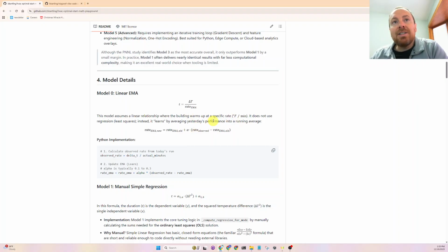So this is exactly what the Tridium optimal start block does not do. It only updates your previous degree per minute, which we kind of looked at briefly on the first video, decompiling the Java code base for that. But now we can look at still the same linear model, but actually cache a few days' worth of degree per minute data.